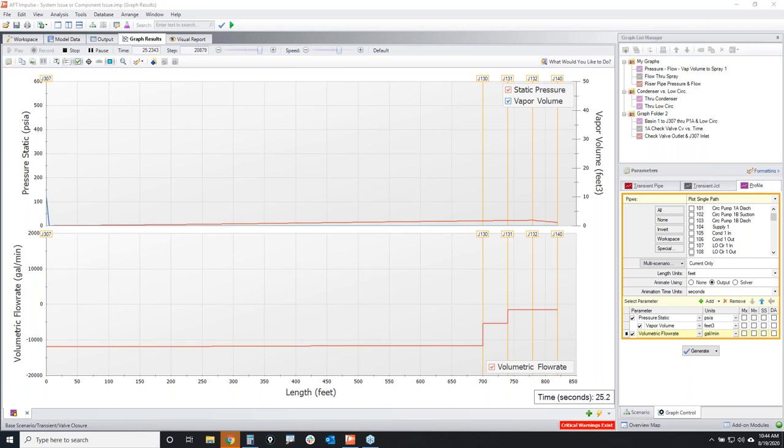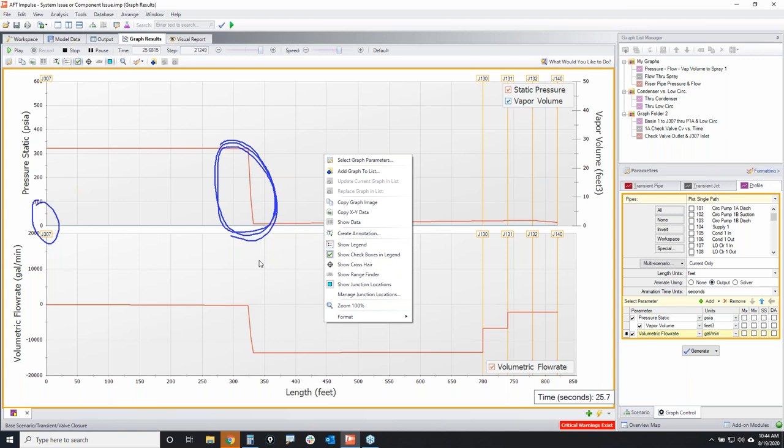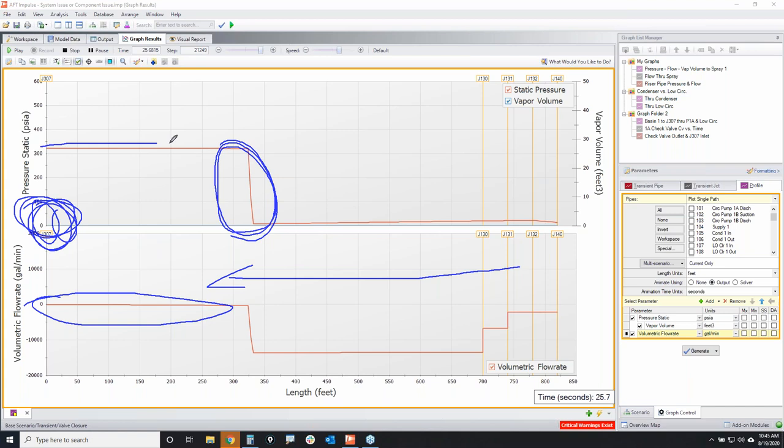where reality is not going to reflect that mathematical model. So when you see that this is just about to collapse right here, and we have that really large pressure spike, this pressure surge wave that you see, that has happened after your liquid has left the system. So when it comes back up to zero, that's because it's thinking that you have liquid that is squishing that bubble. That's what made it pop right here and caused the pressure surge to start passing down the pipe.